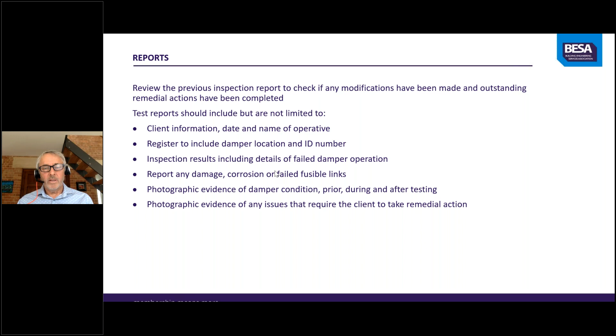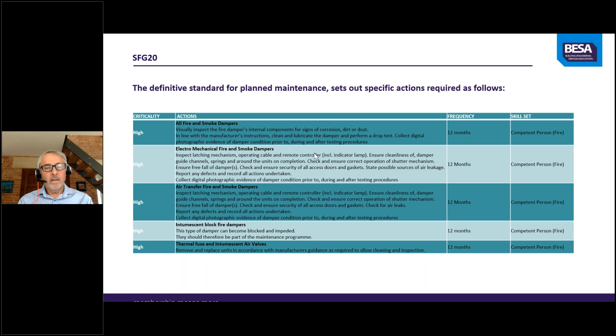SFG 20 is the BESA definitive standard for planned maintenance and sets out specific instructions required for various things. And this is the recommendation that asks for all fire dampers and smoke dampers, electro mechanical fire and smoke dampers, intumescent fire dampers, air transfer dampers, or thermal fused intumescent air valves. And you'll see that all of these dampers have a critically high level of maintenance, and they should be maintained frequently as a minimum of 12 months. And that maintenance should be carried out by a competent person with the right skills for this particular duty. I'm hoping that perhaps one of my colleagues on the panel will actually be able to throw a bit more light on competent persons and training. So we'll hopefully come back to that later on. Next slide, please, Martina.